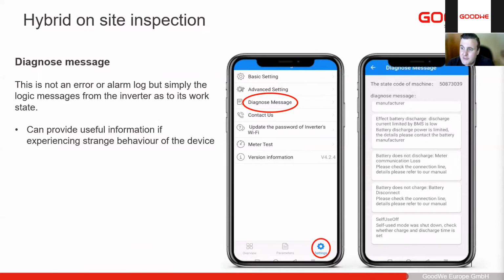Next, there's diagnose message. This sometimes gets confused with alarms, because the alarms are under parameters, alarms. Customers very often come to diagnose message and create a support ticket: "My inverter is having so many alarms, please help me." Diagnose message is not alarms, it's logic messages. So yeah, the inverter is just saying, I am doing this because of this.